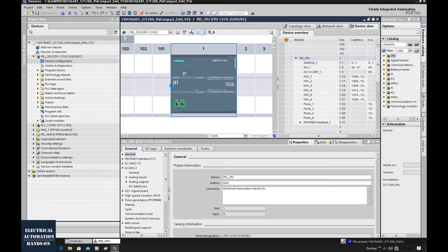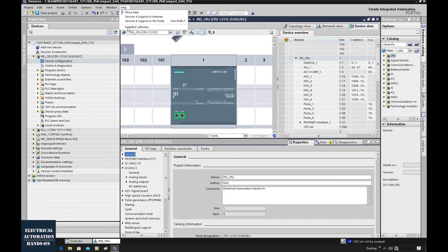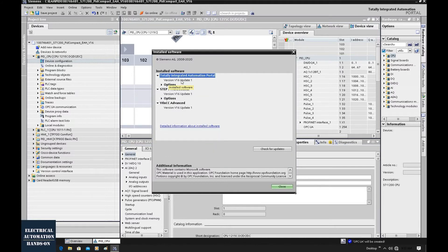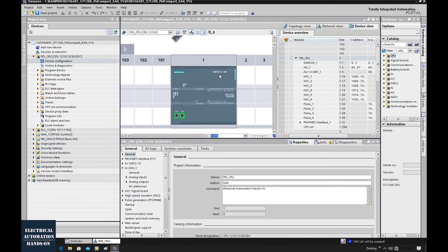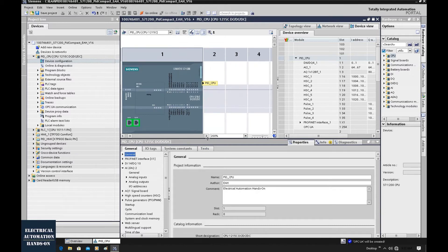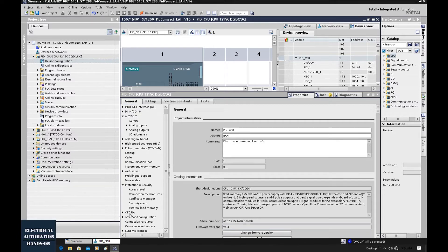You must guarantee your hardware configuration as well as your actual hardware firmware is version 4.4 or greater. So the TIA portal I'm using is version 16. Let's check the hardware configuration — double-click this CPU and you will find the firmware version is now version 4.4. It is the offline configuration firmware. Now let's go to the OPC UA option.